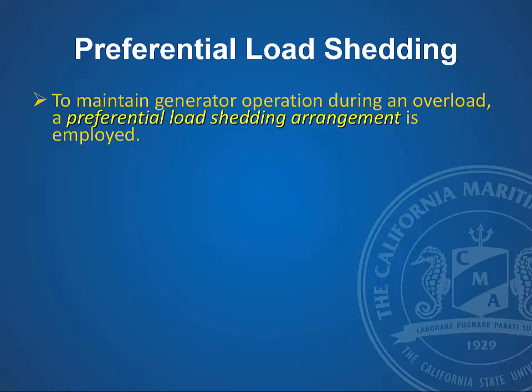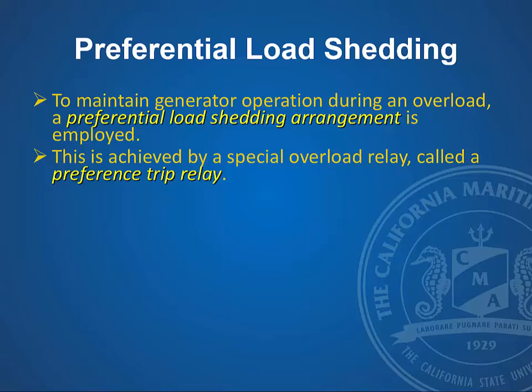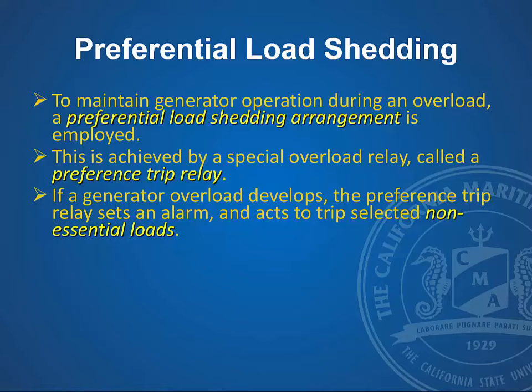So typically what will happen is that if it's a minor amount of overload, then the motorized circuit breaker, the disconnect circuit breaker for that generator, can overload for a short period of time while giving the other generator, the standby unit, time to come up on the line. If it's more than that, then you have these preferential trips. What the preferential trip does is, if there is an overload that could cause a blackout situation, it will detect that, and if there's not enough time for the other generator to come on the line, it will shed these non-essential loads.